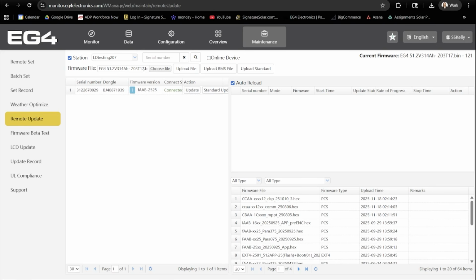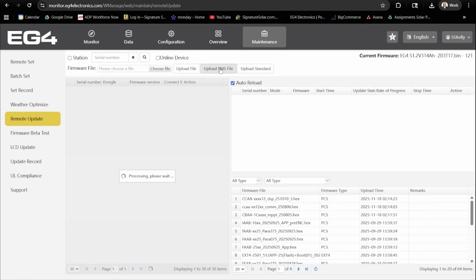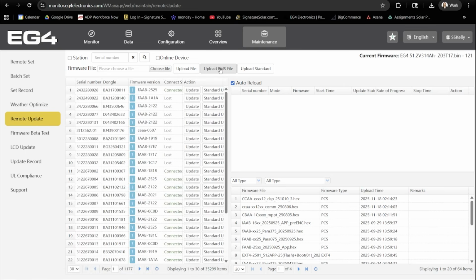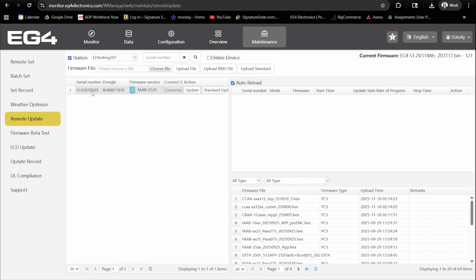Once you have confirmed the file is correct, click Upload BMS File. This uploads the firmware file to the portal in preparation for sending it to the inverter and battery. After the upload completes, confirm that the correct file is listed. Do not proceed unless you are confident the correct firmware has been selected. Identify the master inverter in the system. Click Update in the action column for that inverter.